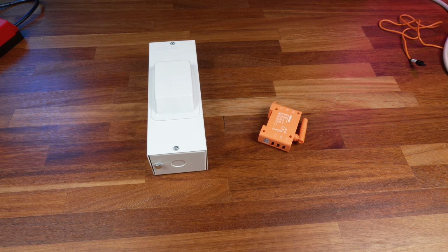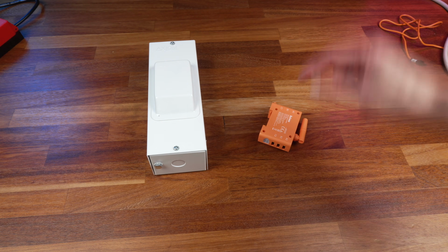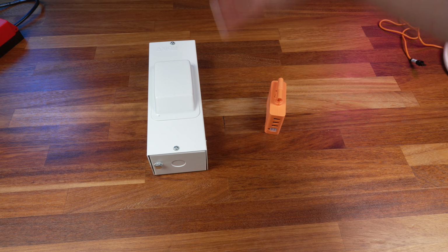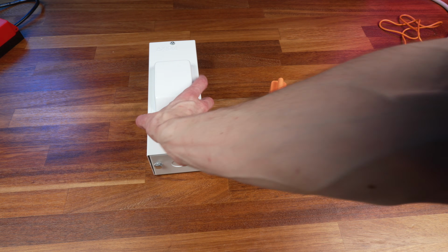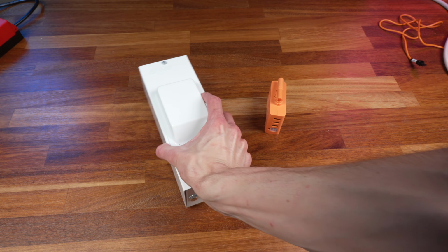So now it's time to install this. As I mentioned earlier, I'm not going to install this inside my consumer unit, I'm going to install it in an enclosure next to it, and then I'll run the CT cables into the consumer unit. So we have the energy monitor here, and for an enclosure, I've got this little enclosure here. This is a cheap little Axiom branded 2-module DIN rail enclosure. It's a cheap thing from Toolstation.